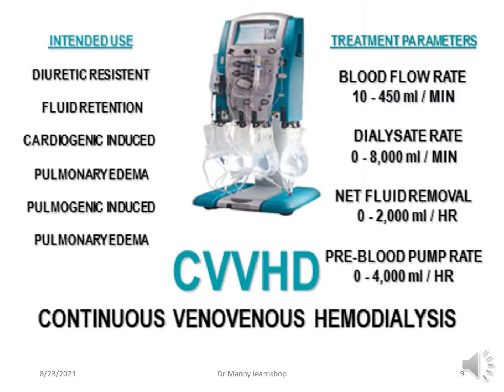Then you've got CRRT, continuous veno-venous hemodialysis. Intended uses are basically the same. Parameters, blood flow rate is similar, if not the same, 10 to 450 mils per minute. Dialysate rate is 8,000 mils per minute, up to. Net fluid removal can still be up to 2,000 mils per hour, and the pre-blood pump can be used, if wanted, up to 4,000 mils per hour.